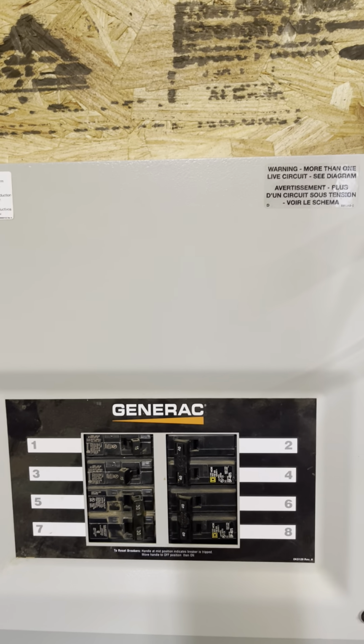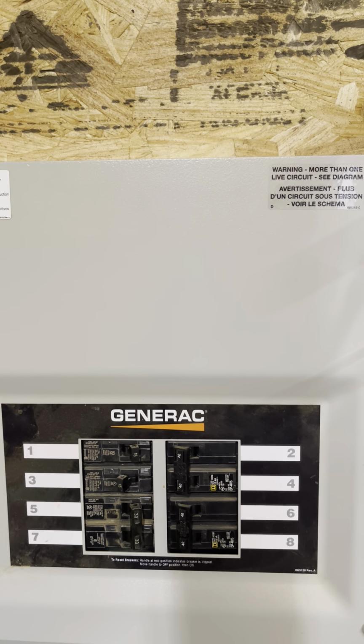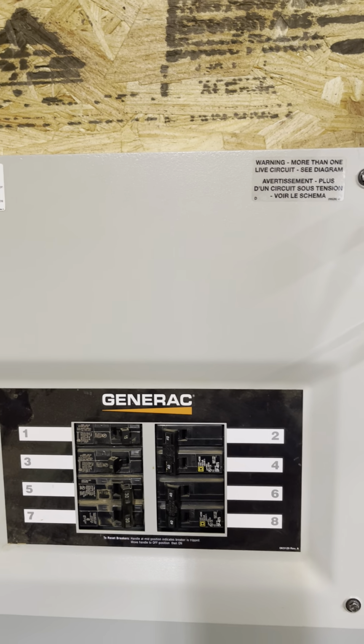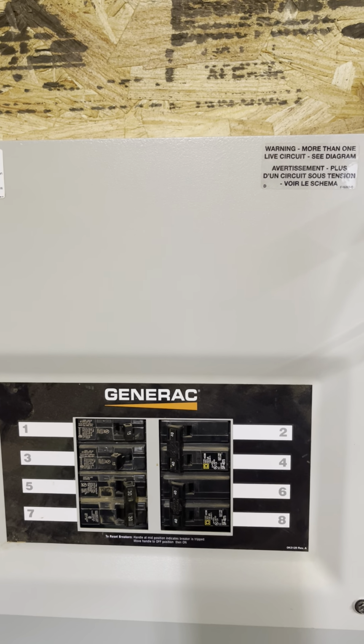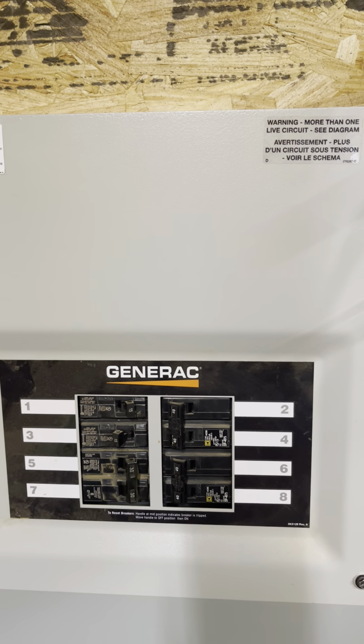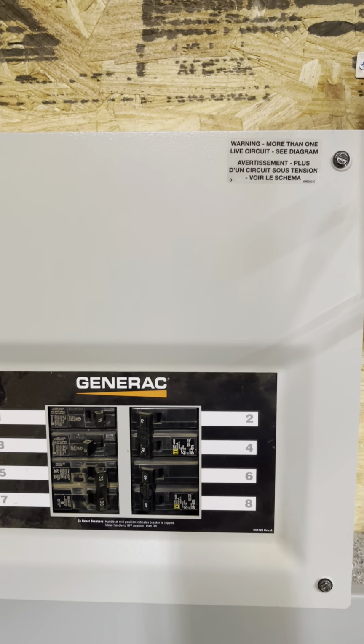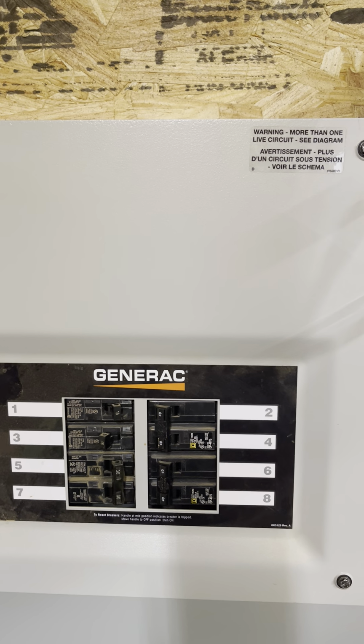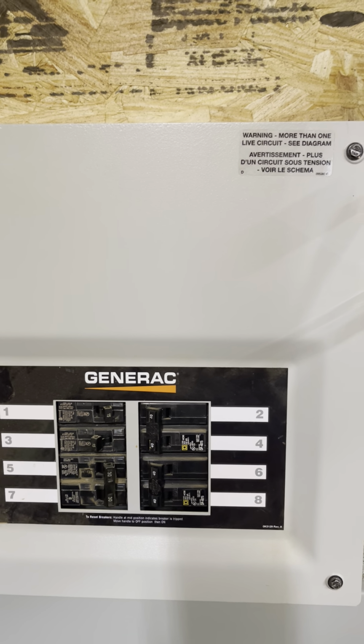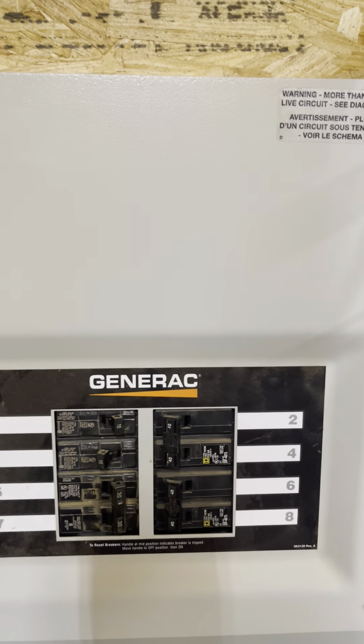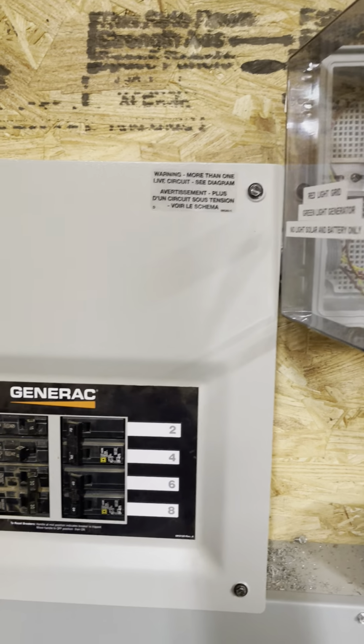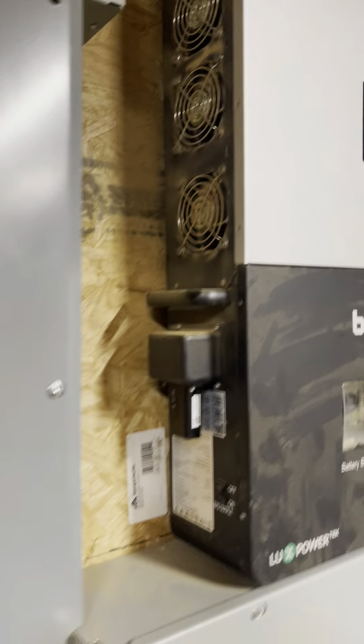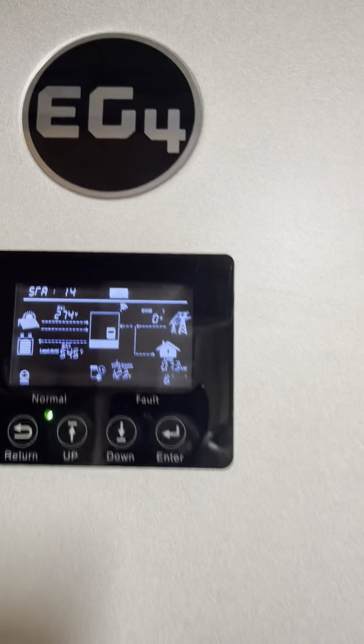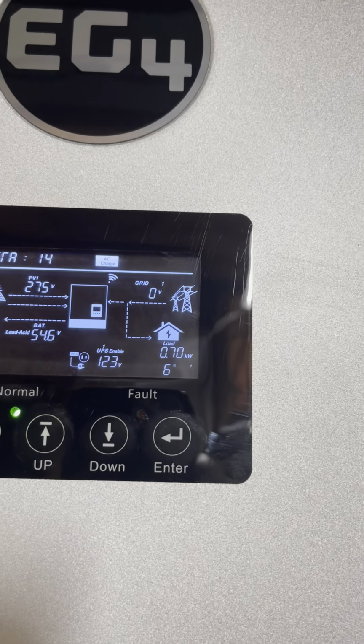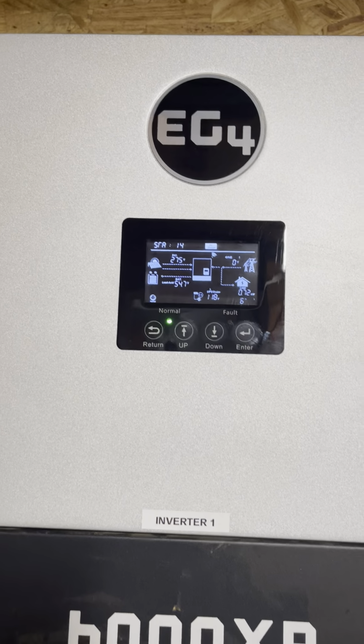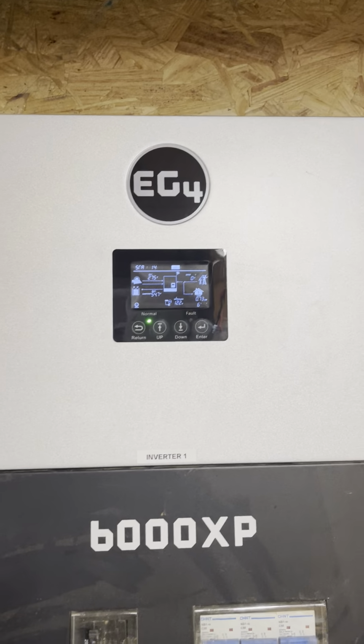The generator is going to run for about 30 seconds, and then this automatic transfer switch will switch over. It likes to warm itself up. And there we go, we just switched over, and now the generator is feeding into the inverters. I can hear it pull down. If I come over here and look at this, between PV and generator, it looks like I'm bringing in around 7,000 watts. And current battery is about 54.7.